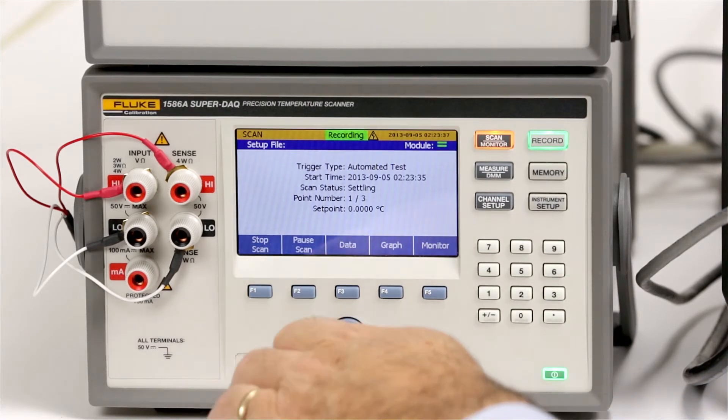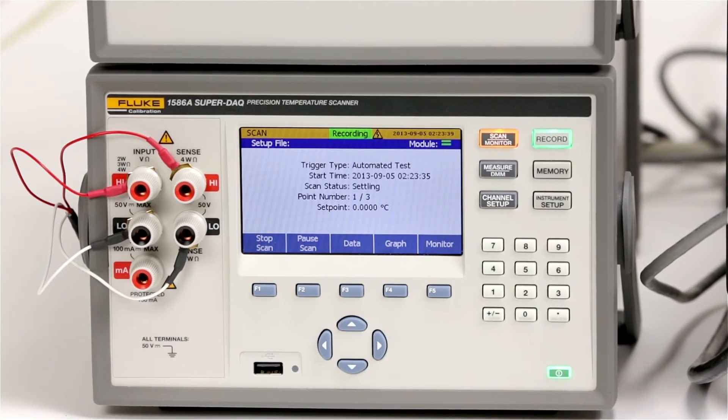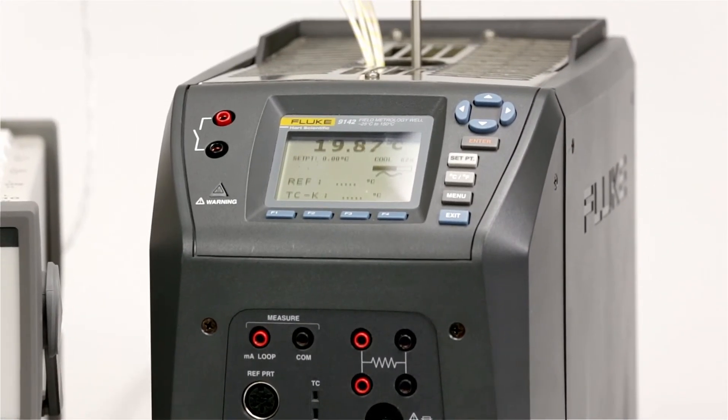The Super-DAQ will automatically record data once the dry well has stabilized and will then advance the dry well to the next program set point temperature.